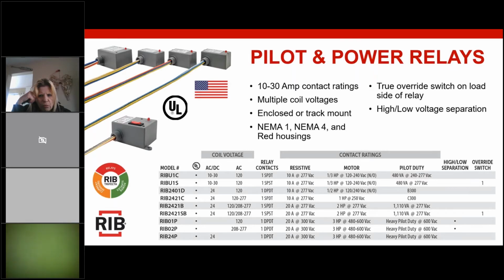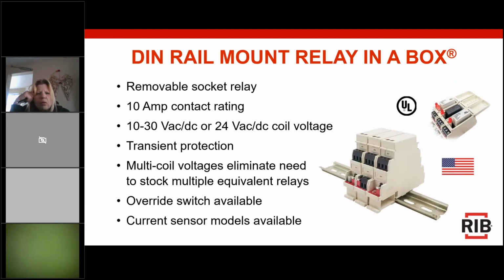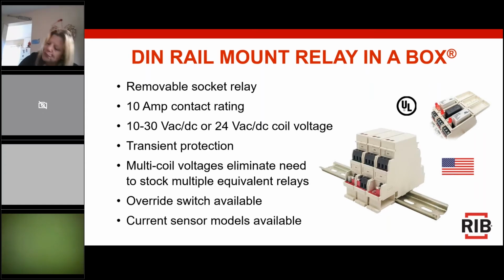One thing we have introduced in the last couple of years, after hearing a lot of customers ask for it, is our offering of a DIN rail mount relay. We've had panel mount relays in the past, but they were not necessarily the DIN rail style. So we came up with ours. It has a removable socket relay with a 10 amp contact rating. It's available in two different voltage ratings, either 24 AC/DC or 10 to 30 AC and DC.